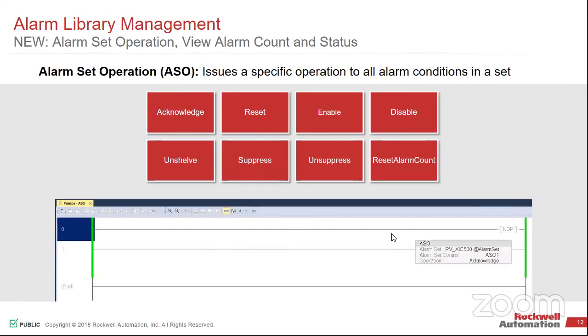The only issue that you will run into is if you're trying to use a PanelView Plus 7. The PanelView Plus 7 does not subscribe to our alarm and event server, meaning that it has no ability to grab the alarms out of the controller. So this would be what we would tie in with FactoryTalk View SE on the computer side of it, whether it's standalone or distributed DCS. So if you've got the SCADA, if you've got anything on there, we're perfectly okay. It will go back all the way down to version 9 of FactoryTalk View SE.